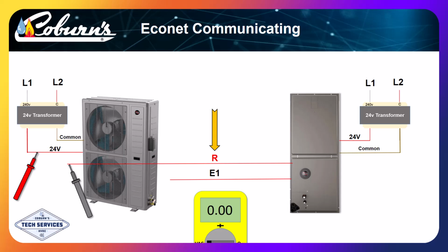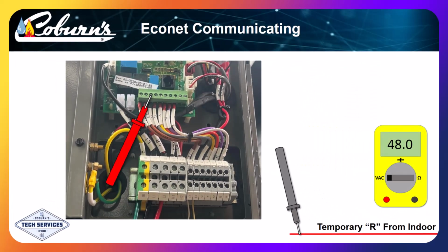Since the two transformers aren't usually very close to each other, we can temporarily connect one of our communication wires to R at the indoor equipment and check both R conductors outside with a meter. We power up both pieces of equipment and take our measurement. At this point, there shouldn't be any other control wires connected between the equipment. The 24-volt R can be found on the control board in the outdoor unit labeled as R.